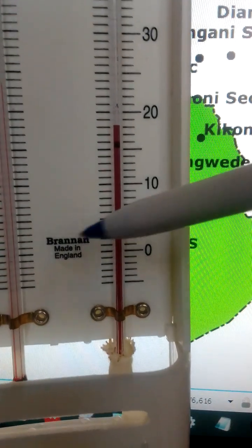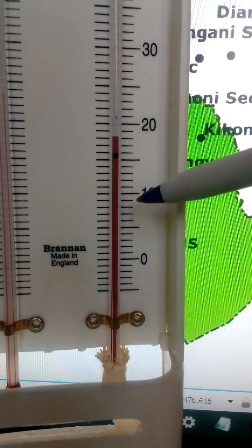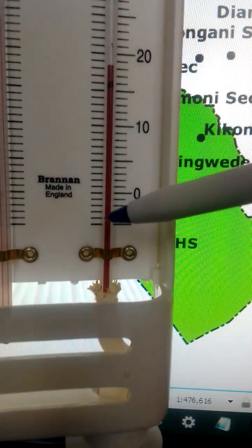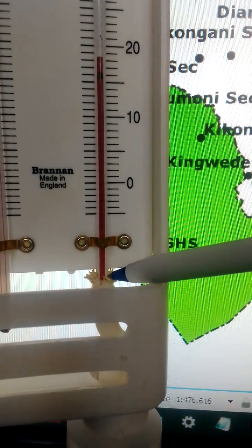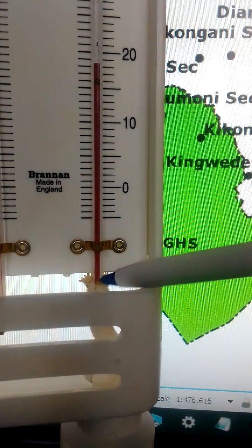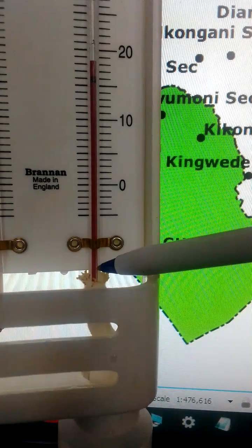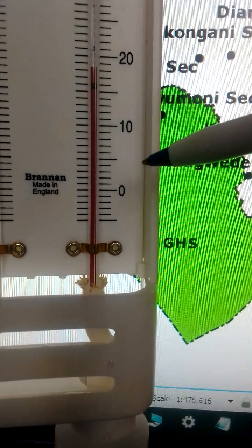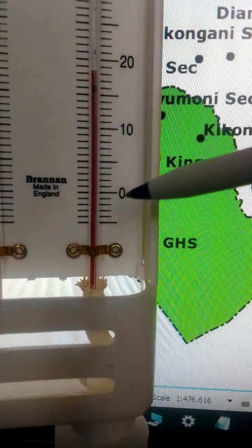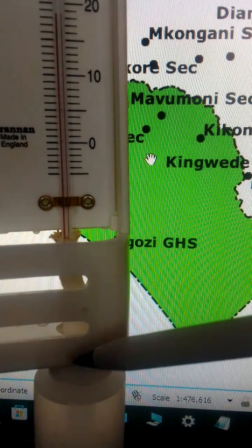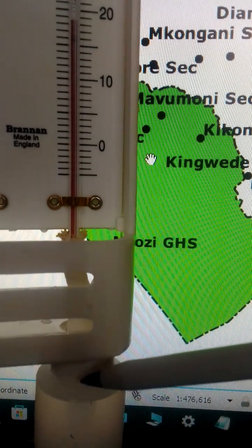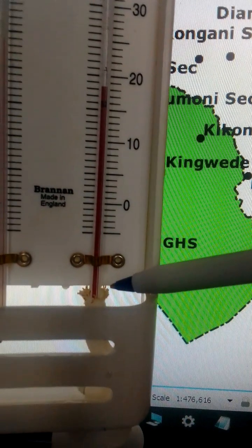We find that these two thermometers are ordinary mercury in glass thermometers. Now, at the wet bulb, we tie a muslin cloth, alright? And then on that cloth, we tie a wick or strands of cotton threads, which are immersed in distilled water in this container, right? So the water rises by capillarity along the wick and evaporates.